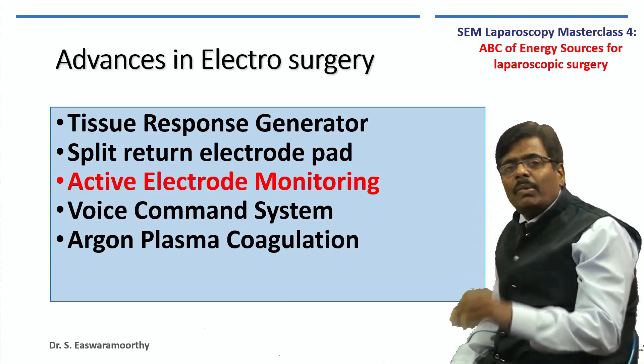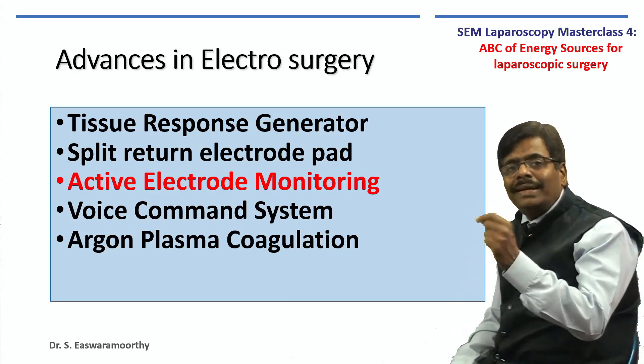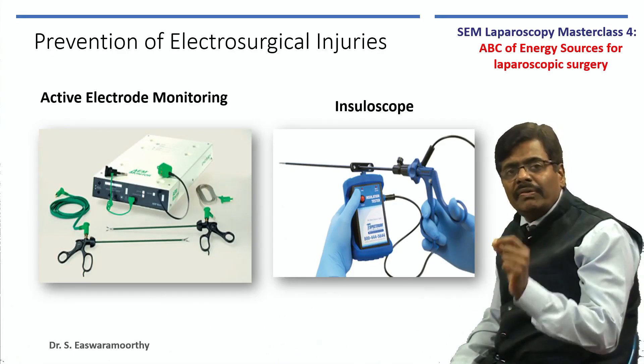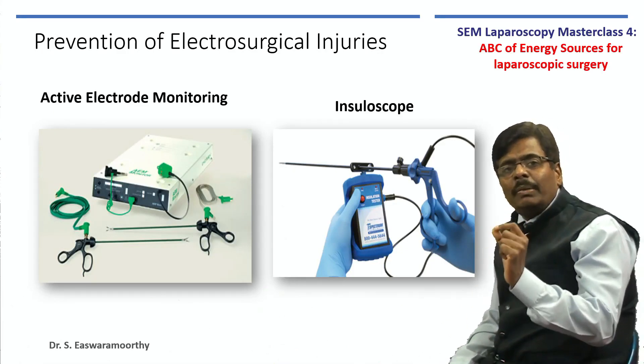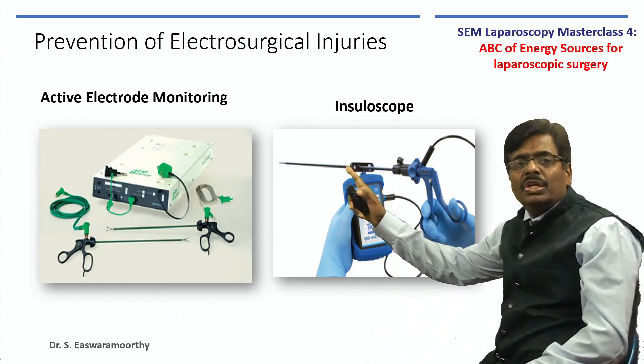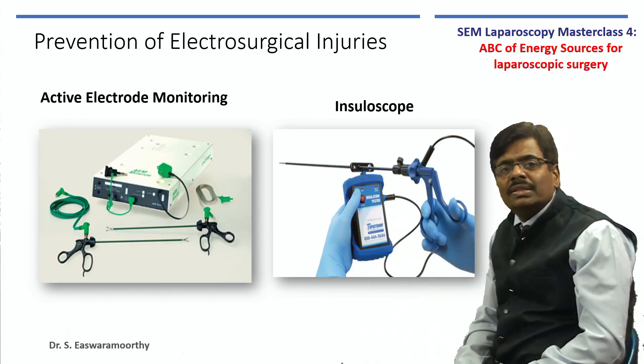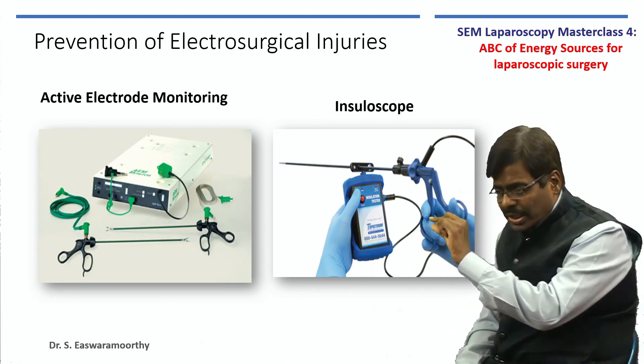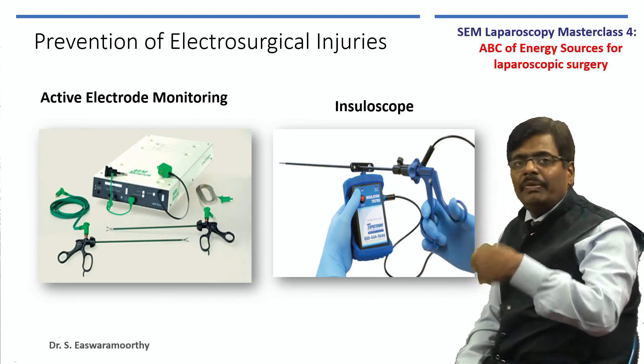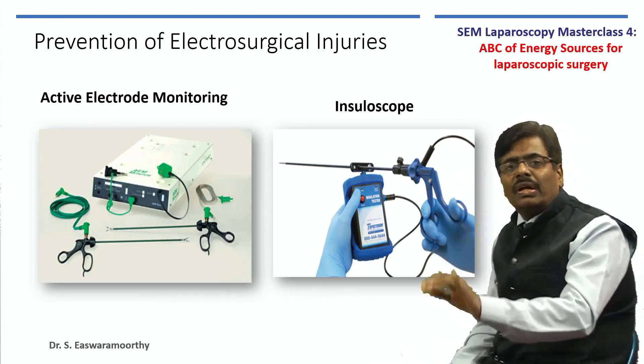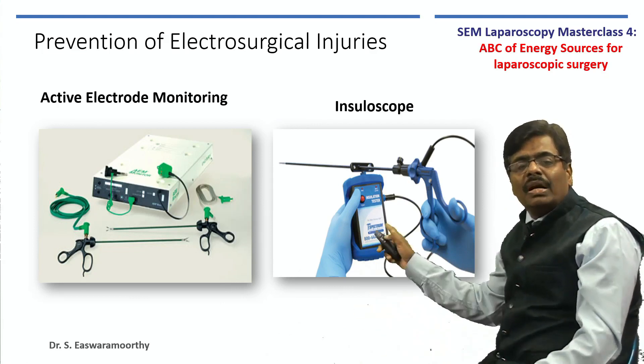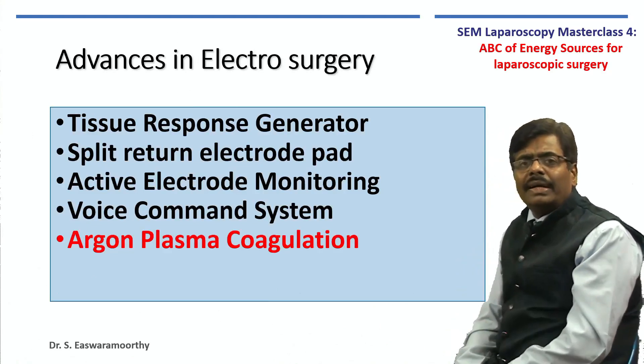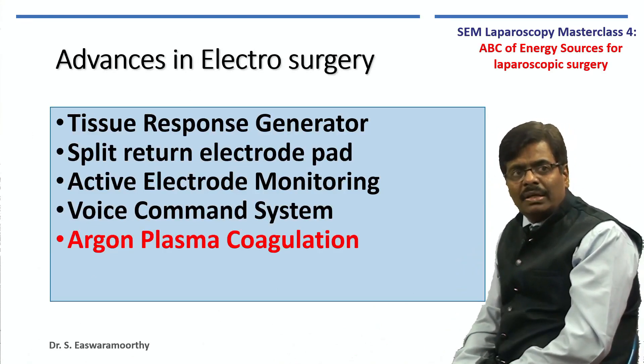There are also gadgets available to monitor the active electrode for insulation damage — equipment like active electrode monitoring devices or insuloscopes that emit a beep whenever there is a breach in insulation. These are very valuable. However, as mentioned earlier, a simple magnifying glass used to carefully inspect every sheath before sending instruments for sterilization is good enough in most settings where high-end gadgets may not be affordable.